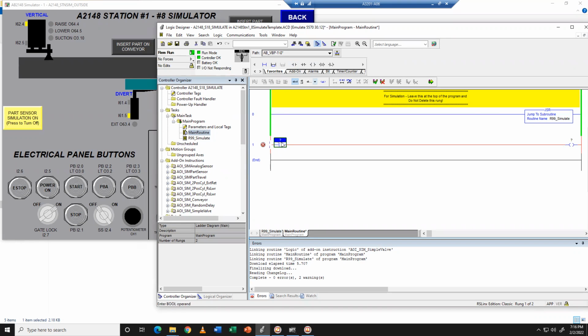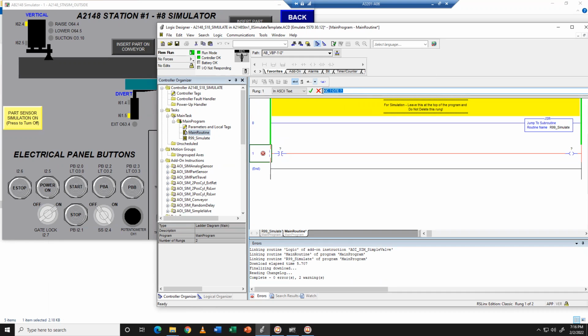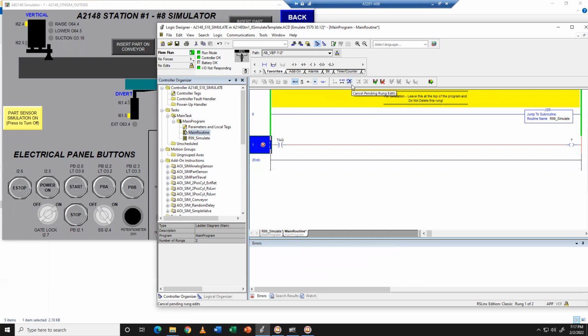So I dropped my evaluations in there from the palette. Another way that you can make changes is if you're online, you can see this red line is being edited. You can also see that these I's is being, I forget what I stands for, but it's under construction here. If I double click, it pulls up this text box. So you can also type in the different operands that you want. So XIC is examine if closed. The question mark is the tag, and OTE is an output energize, and the question mark would be its Boolean tag.